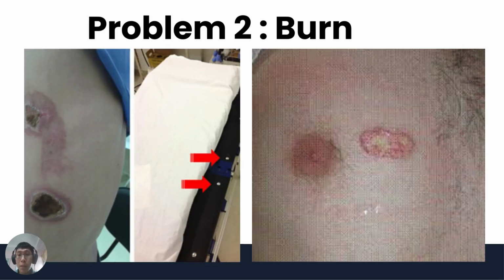The second problem is burns. Skin burns are the most frequently reported, and frequently happen at the return electrode site. Partial or complete detachment of the electrode pad from the patient is the most common issue. Patient burns can be a result of dense creases or bends in the surface of the return electrode. They can create local hotspots of high density current. Electrosurgical units are equipped with protective features designed to minimize the risk of patient burns that may occur due to issues related to return electrodes.